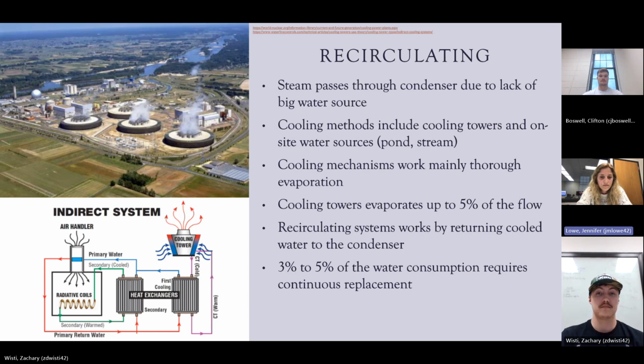Next is recirculating. Recirculating is steam that passes through the condenser due to lack of a big water source. Cooling methods include cooling towers and on-site water sources such as ponds and streams. Cooling mechanisms mainly work through evaporation. Cooling towers evaporate up to 5% of the flow. Recirculating systems work by returning cold water to the condenser, and 3 to 5% of the water consumption requires continuous replacement.